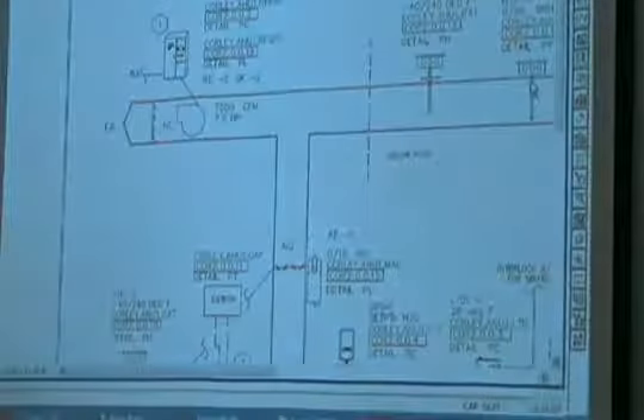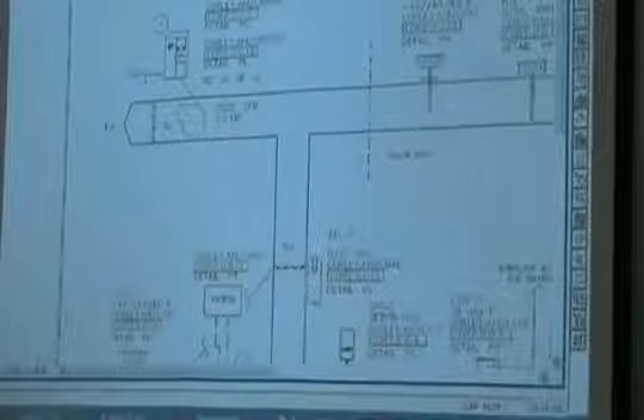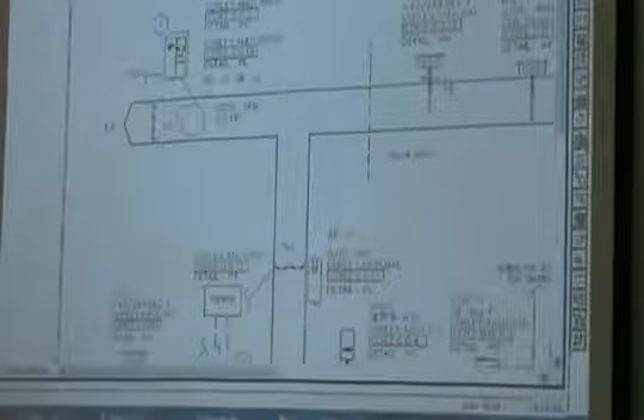Now, one thing that people will do is they'll take the return air humidity that's right here and the return air dry bulb temp, and calculate the enthalpy of the air, which is basically the heat content of the air. And then we'll take the outdoor humidity and outdoor dry bulb, calculate the enthalpy of it, and switch over based on enthalpy. Sometimes that gives you a more energy efficient switchover instead of just a dry bulb alone. So now we've also thrown in a relief fan and a drive on it, and it's going to have another job to do. Now let's start going through this, just to make sure everybody sees it.